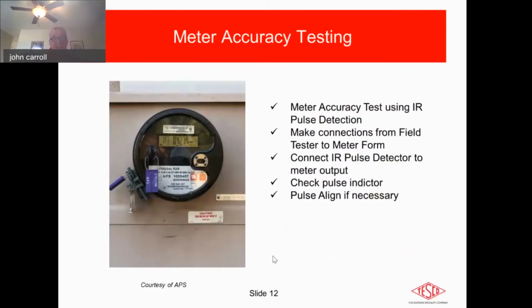So doing a meter accuracy test, we want to be able to pick up the pulse, and that's a prime concern. And this is courtesy of APS. I did a test with them not too long ago. We're using IR pulse detection from the front of that. In this particular case, this is a Form 9 meter. So we're picking it up from the front, and you can see the indications on the screen. So there's a lot of good information that's available for you there.